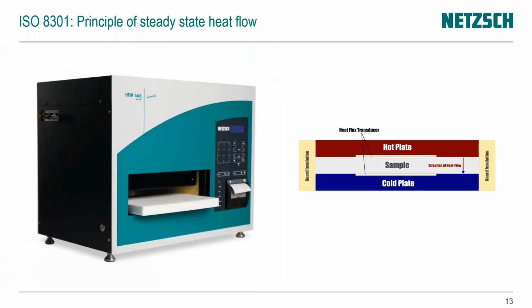The principle of the measurement you see here: you see in the chamber a sample coming out. It lies on a bottom plate, and what you see is the top plate and the guard insulation around it. The plate on the top is the hot plate. The plate on the bottom is the cold plate. You can do it also vice versa. Between them, you insert the sample, which is in contact with heat flux transducers. And those heat flux transducers are able to measure the actual heat flow through the material.